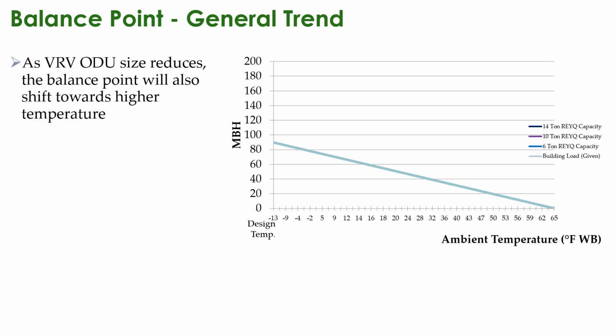As a general trend, the variable refrigerant system balance point is going to shift higher as you reduce the capacity of that outdoor unit. So as I said, you can size to hit 100% of your requirement at your design condition, but you have to look at the factors of how oversized that is on the cooling side, and is the juice worth the squeeze, if you will, on the cost of the project. So adding more equipment adds more indoor gear typically, adds more outdoor gear, more electrical, more weight, all of those factor in.